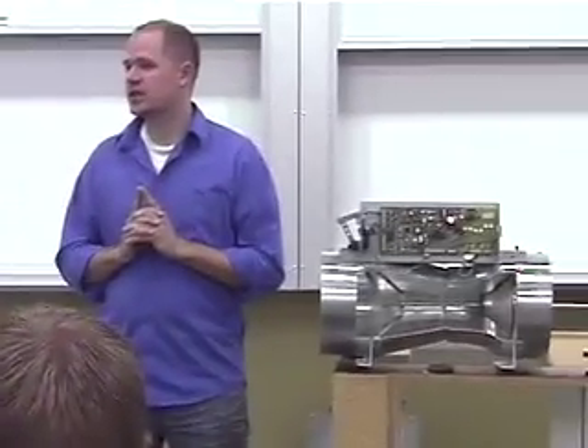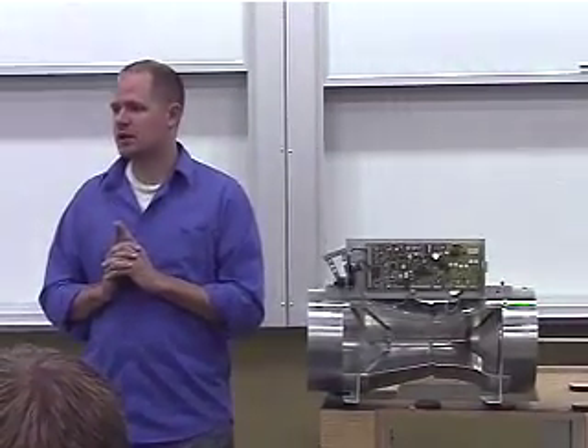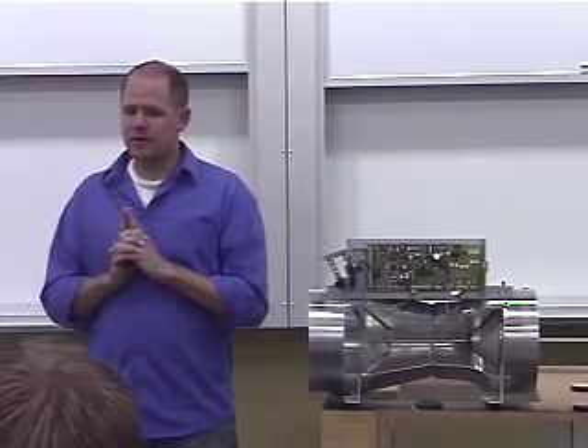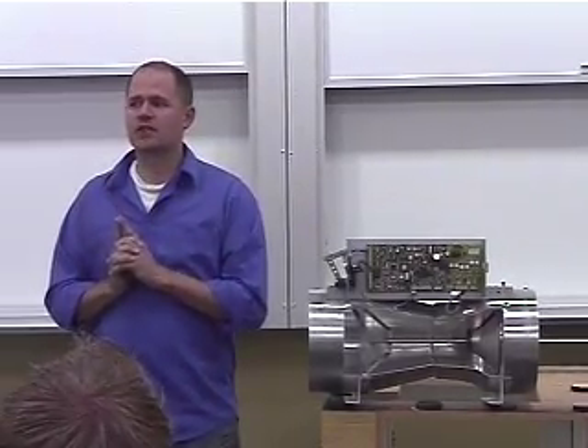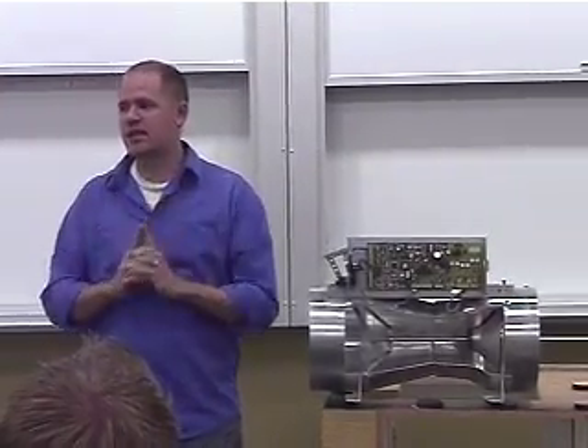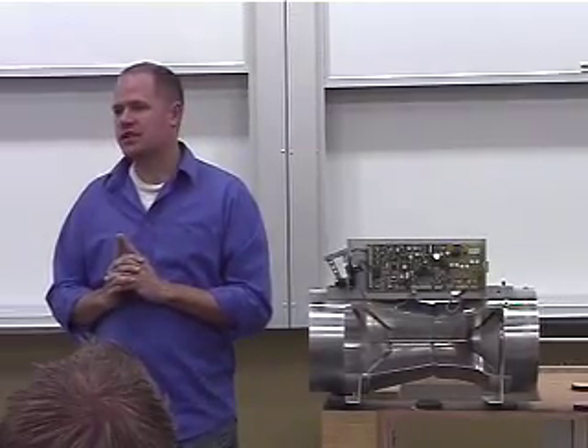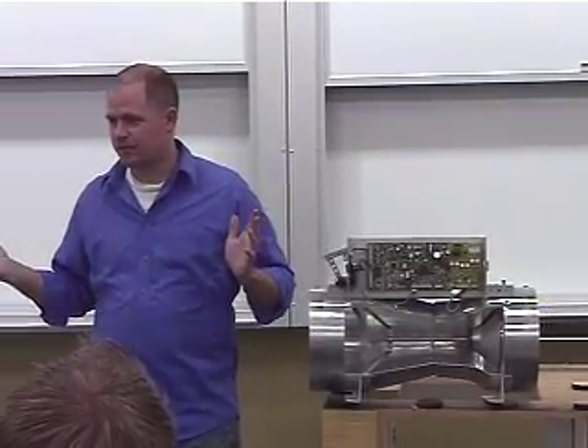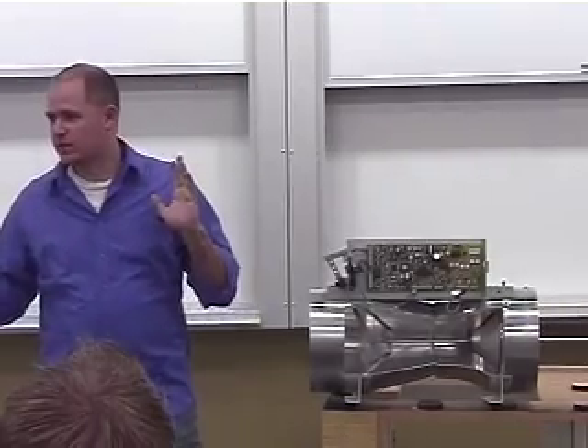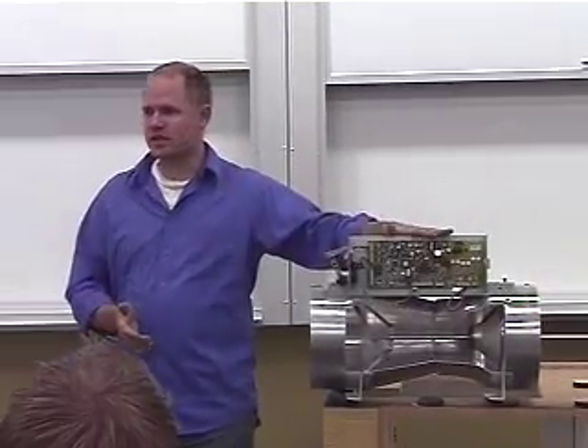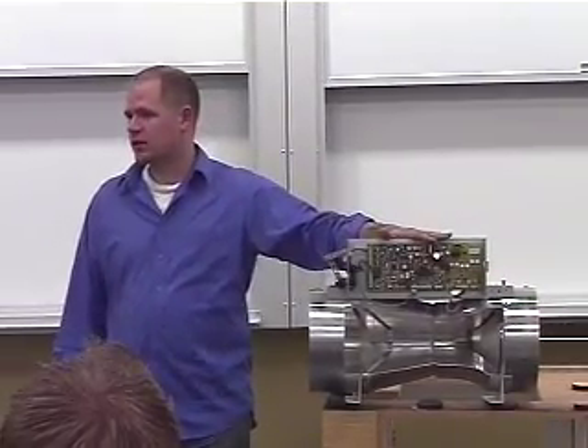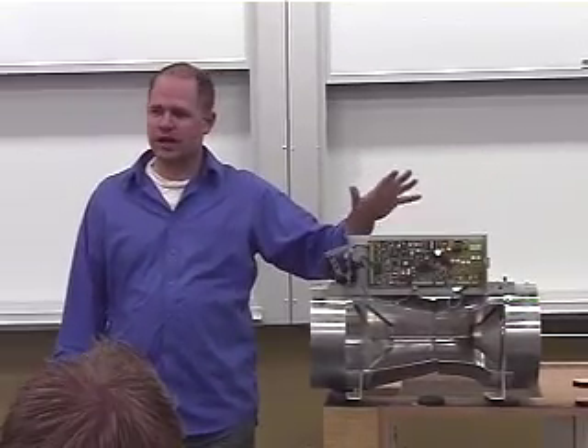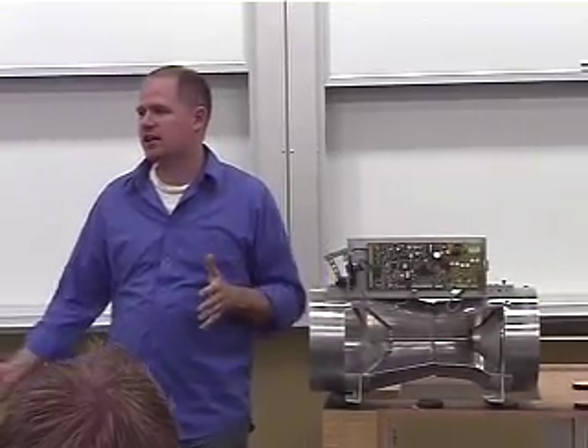It goes to the position that it fails the safest in. Typically, every job I've done that has fume hoods, the fume hoods are not supposed to have fire dampers between them and the exhaust. But if they shut the fans down, it does no good anyway. So it depends on what they're doing with the fans. These go to the position they need to be in, whatever it is for safety. Any of your low speed stuff is going to be fail in place, period.